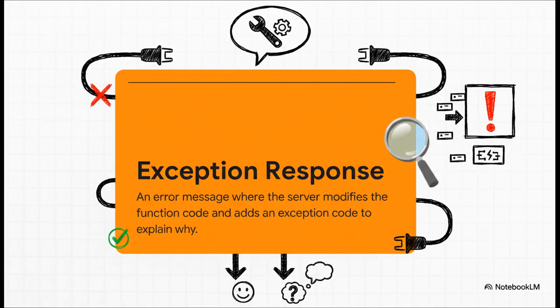This is where Modbus gets really smart. It has something called an exception response. Instead of just staying silent or crashing, the server sends back a very specific error message. It actually takes the original function code and changes it slightly to signal, hey, there's an error. And then it includes a special exception code that says exactly what went wrong, like an illegal data address.